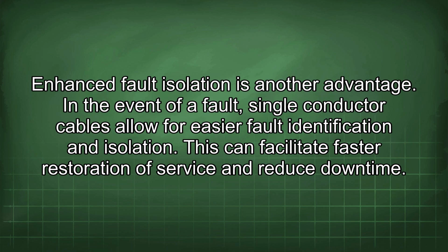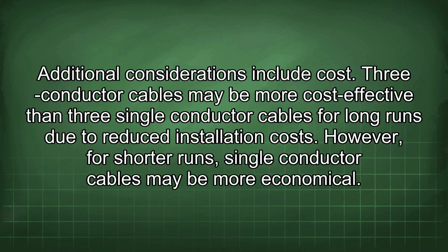Enhanced fault isolation is another advantage. In the event of a fault, single-conductor cables allow for easier fault identification and isolation. This can facilitate faster restoration of service and reduce downtime. Additional considerations include cost. 3-conductor cables may be more cost-effective than 3 single-conductor cables for long runs due to reduced installation costs. However, for shorter runs, single-conductor cables may be more economical.